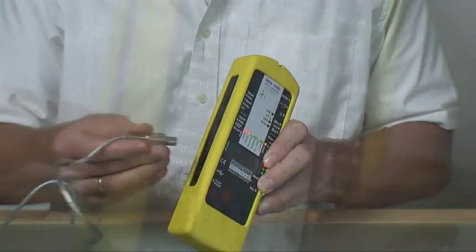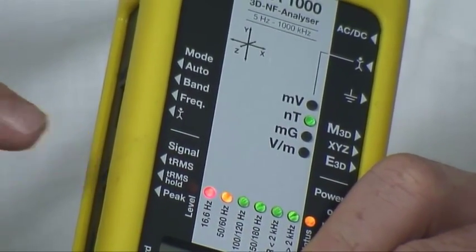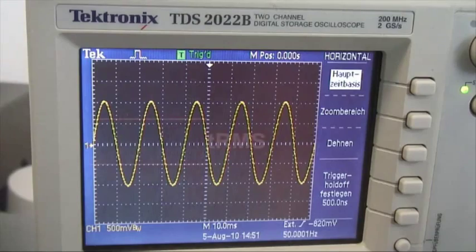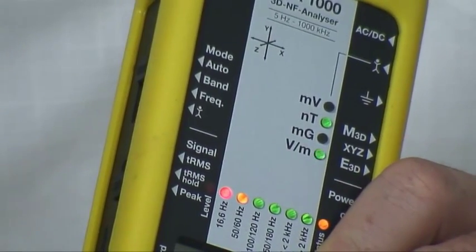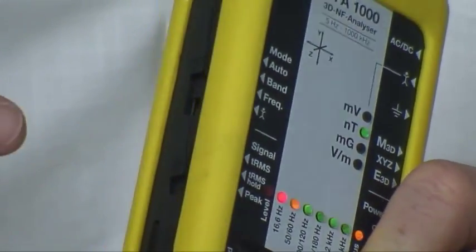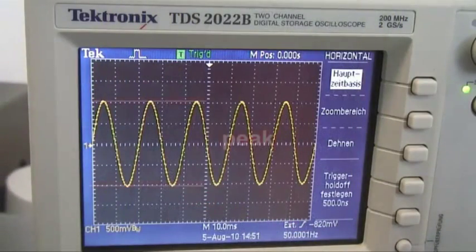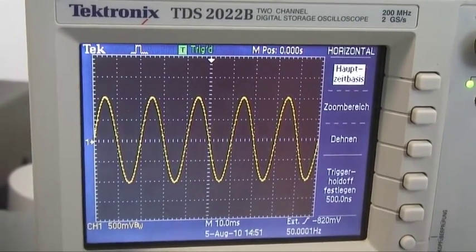With the signal switch you can choose if you want to measure the tRMS, which is the standard position, hold the tRMS with tRMS hold, or choose the peak measurement — realized here for the first time ever at this sensitivity. With peak you will measure up to the real crest of the signal, not the average value. This is very important for irregular pulses or dirty power.